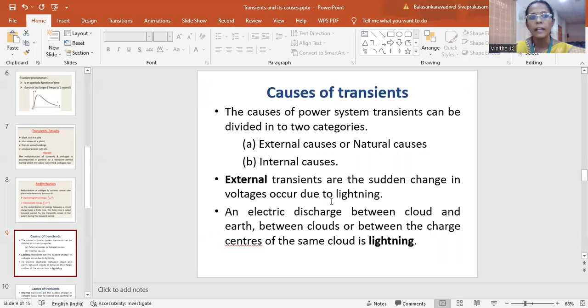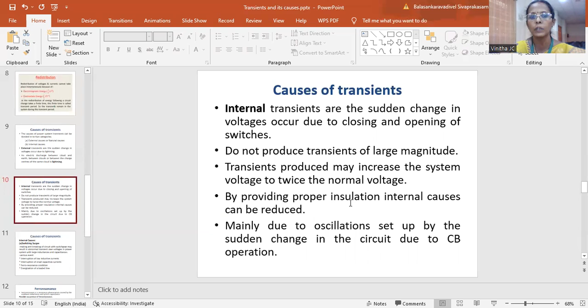The second one is internal causes. As the name itself says, it is internal. During any switching operation, if transients are created, they are termed internal transients. Normally, this is due to opening and closing of the switches. Compared to the external transients, that is lightning, the magnitude of the internal transients is less. These transients may increase the system voltage to twice the normal voltage, and these switching transients may be reduced by providing proper insulation in the system.